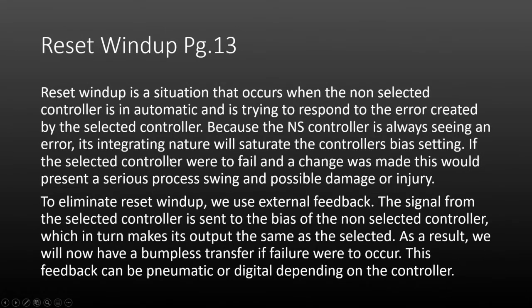If the operating controller were to fail at that point and the switch was made to the non-selected controller, it's going to be showing an error that is magnitudes times worse than it actually is, and you'll get a serious process swing, possibly causing damage or injury. To eliminate reset windup, the solution is simple: we use external feedback, where the signal from the selected controller is sent to the bias of the non-selected controller.